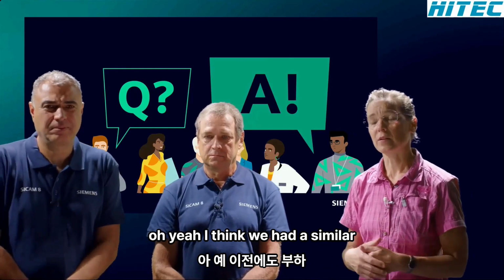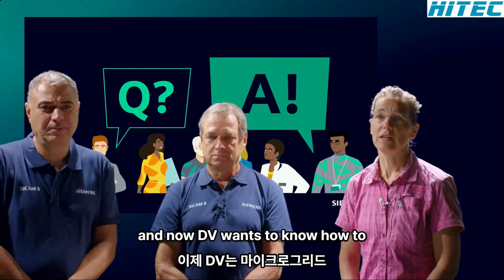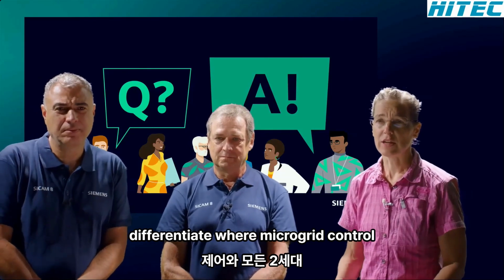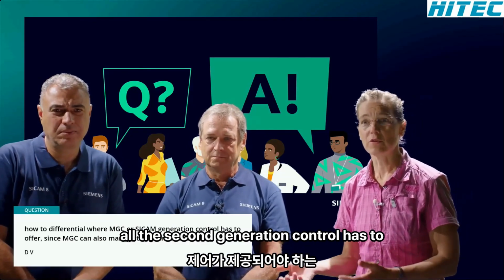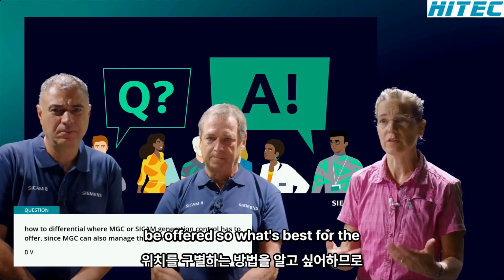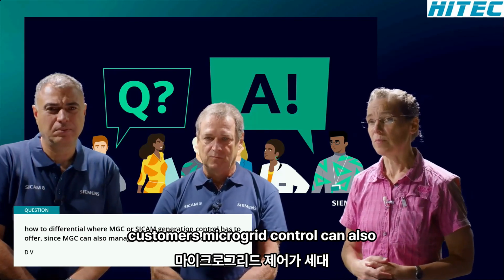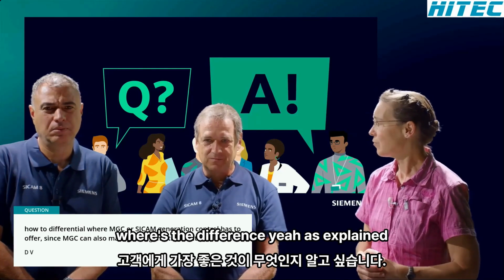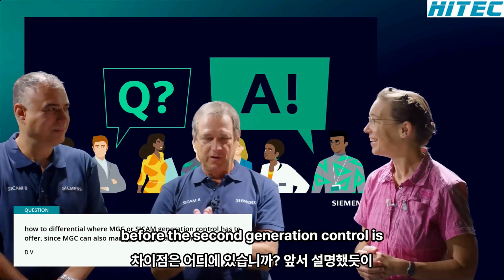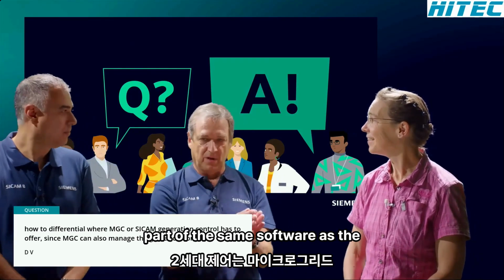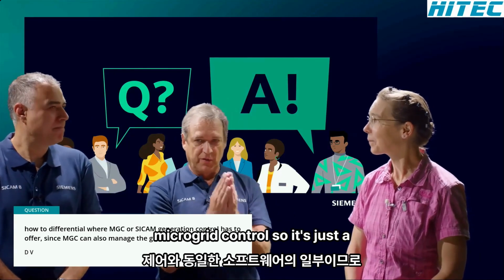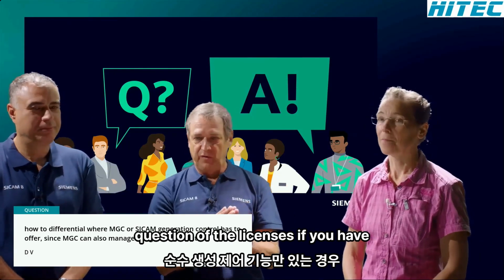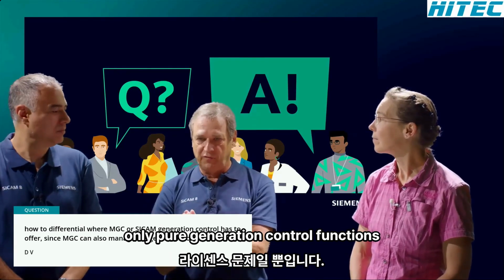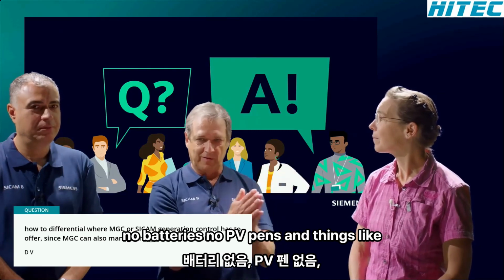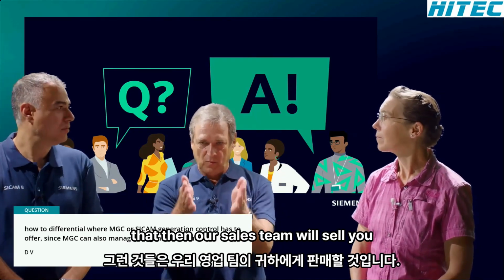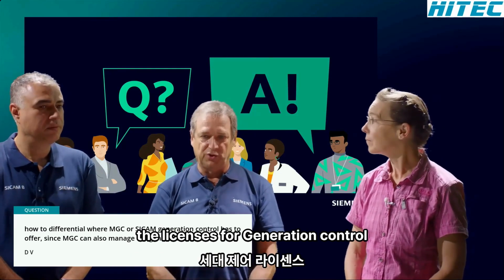I think we had a similar question with load shedding before, and now DV wants to know how to differentiate where microgrid control or the SICAM generation control has to be offered. So what's best for the customers? Microgrid control can also manage the generation control. Where's the difference? As explained before, the SICAM generation control is part of the same software as the microgrid control, so it's just a question of the licenses. If you have only pure generation control functions, no batteries, no PV panels and things like that, then our sales team will sell you the licenses for generation control.